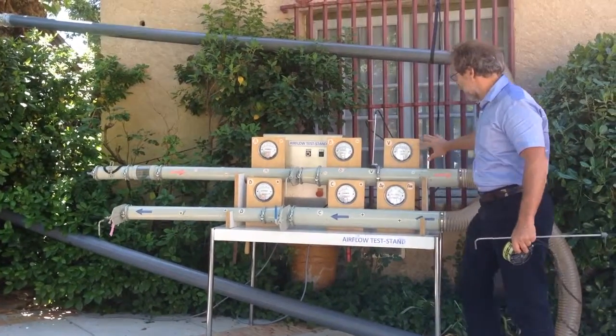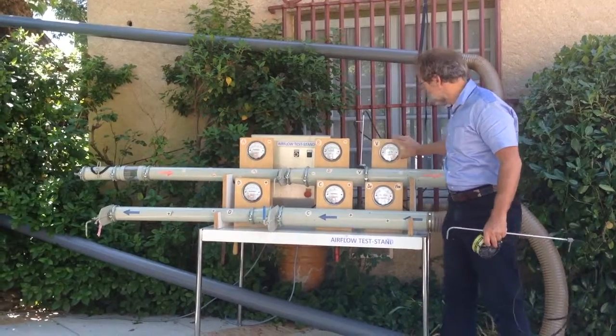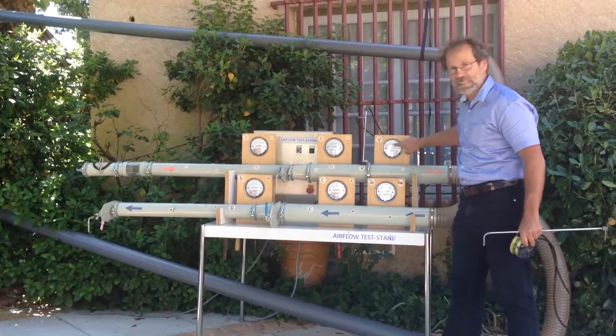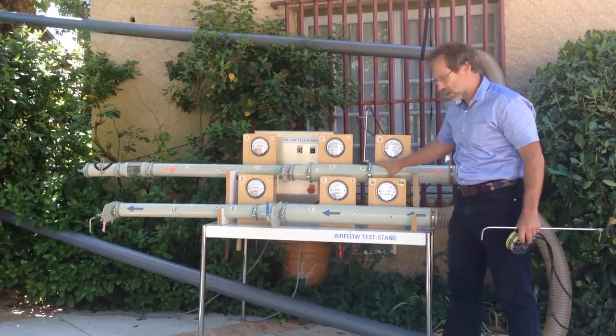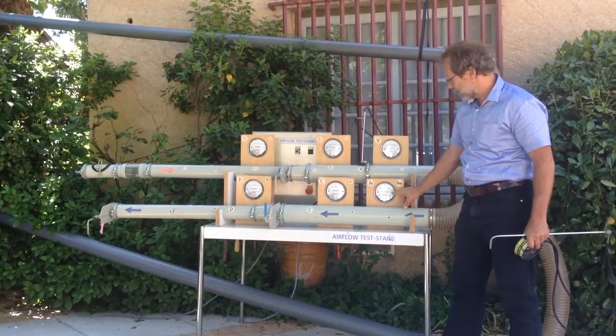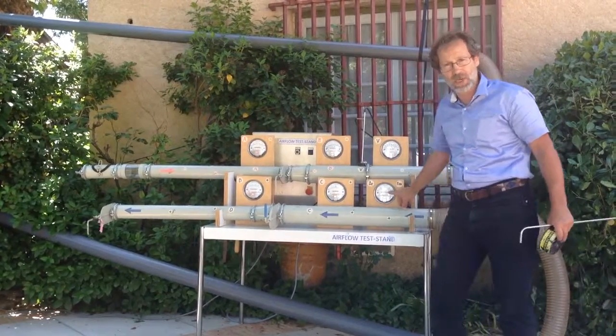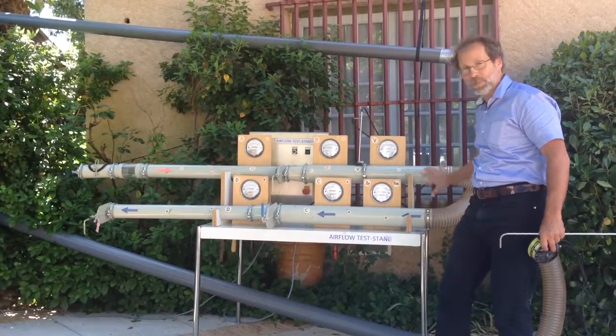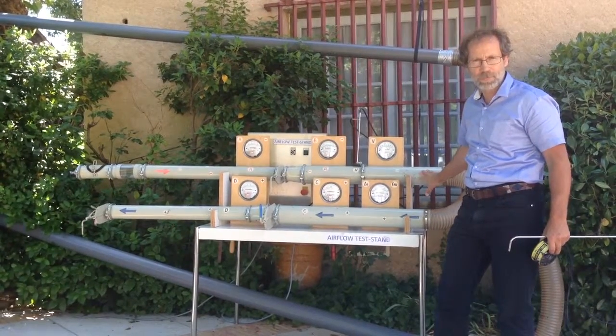Further on, I have installed these instruments. This one is connected to the pitot tube and shows the speed inside this ductwork. That one is installed at the fan inlet and outlet, and it will show the differential pressure across the fan.